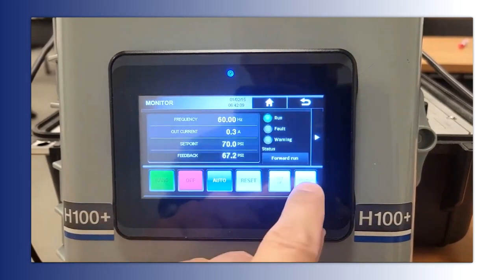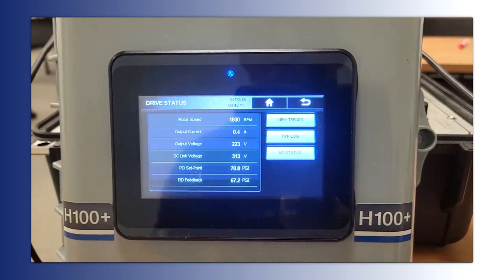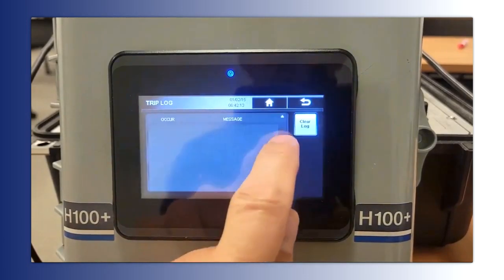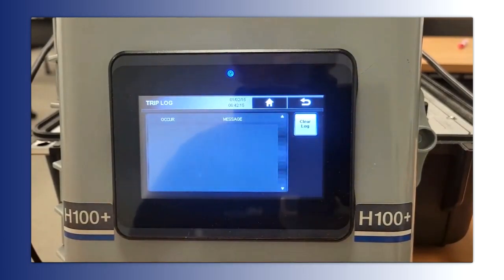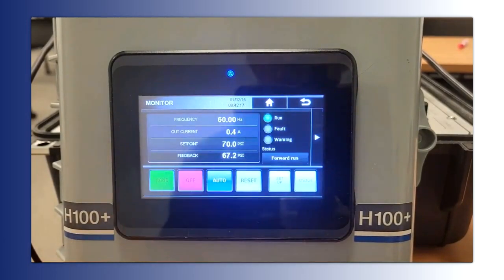You could also see under here the trip log. So there's no trips here. The drive isn't tripped at all. You could also back up parameters into this HMI, and you could also do that on the keypad too. You could back up parameters. So that's just a little demo on PID. So I'm going to stop it.